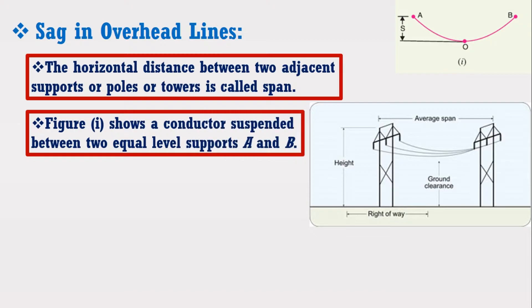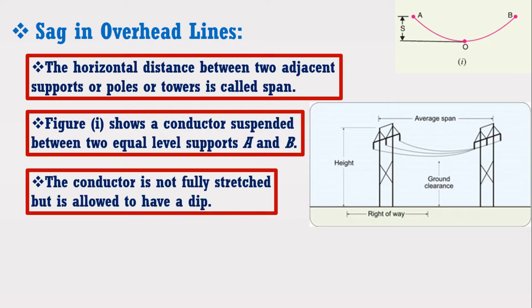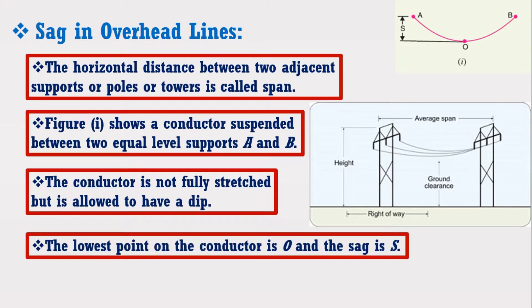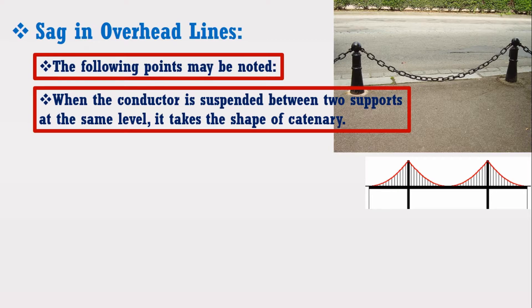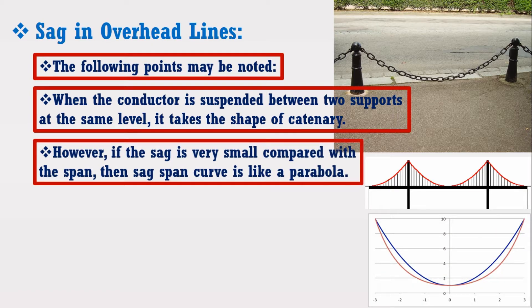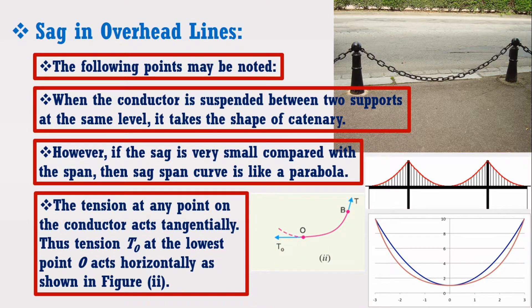Consider figure 1, which shows a conductor suspended between two equal level supports A and B. The conductor is not fully stretched but is allowed to have a dip. The lowest point on the conductor is O and the sag is S. When the conductor is suspended between two supports at the same level, it takes the shape of a catenary as shown in the figure. However, if the sag is very small compared with the span, then the sag-span curve is like a parabola. The catenary shape is a U-shaped curve whereas the parabola curve is a little bit narrower. The tension at any point on the conductor acts tangentially; thus, tension T0 at the lowest point O acts horizontally as shown in figure 2. This is an important consideration in the mechanical design of overhead lines.